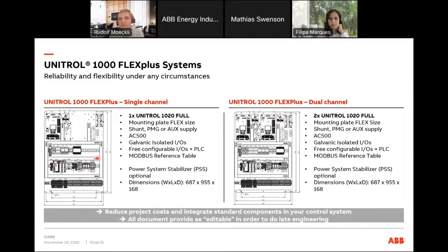What you can select here is single or dual channel functionality. It's suitable for different supply modes: shunt supply, where the generator output is fed back over a transformer to the AVR; PMG, a rotating permanent magnet generator on the generator; or auxiliary supply, coming from a battery or a fixed 400 volt supply, for example.